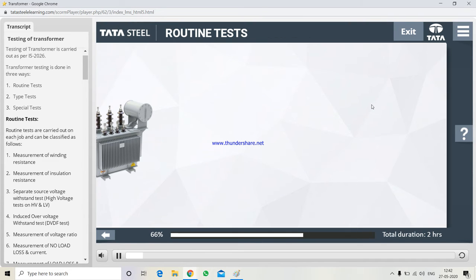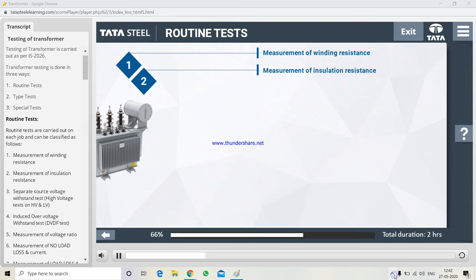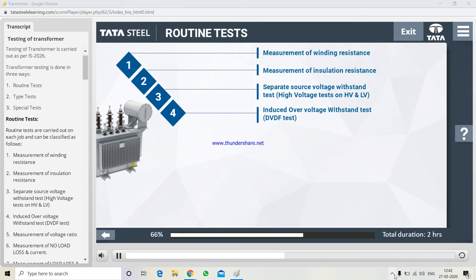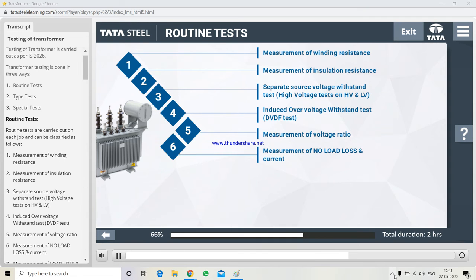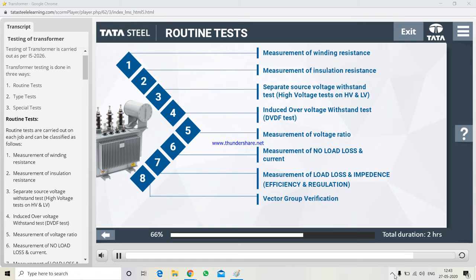Routine tests are carried out on each job and can be classified as follows. 1. Measurement of winding resistance. 2. Measurement of insulation resistance. 3. Separate source voltage withstand test. High voltage tests on HV and LV. 4. Induced over voltage withstand test. DVDF test. 5. Measurement of voltage ratio. 6. Measurement of no load loss and current. 7. Measurement of load loss and impedance, efficiency and regulation. 8. Vector group verification. 9. Oil PDV test. Click each tab for more information.